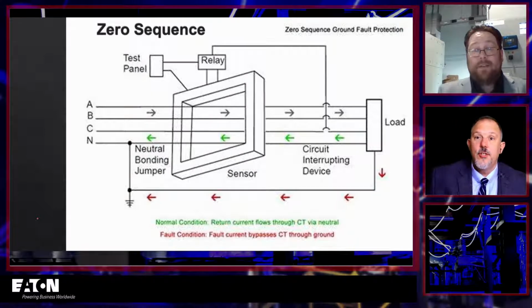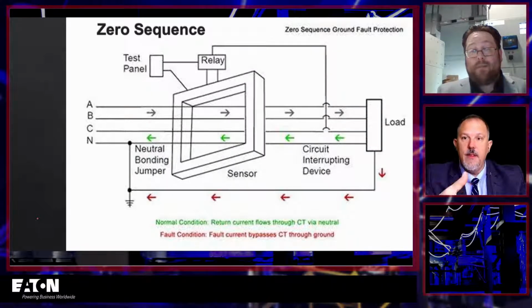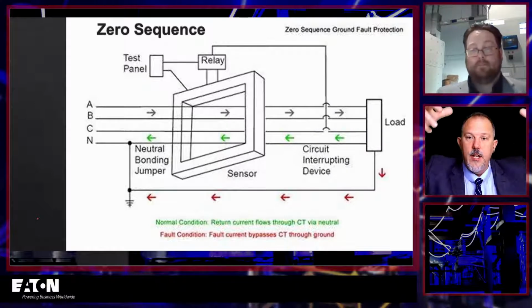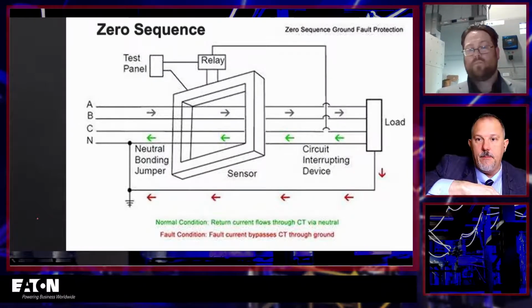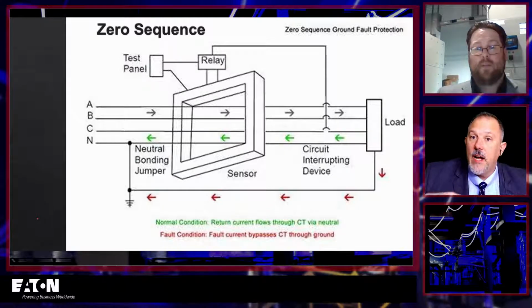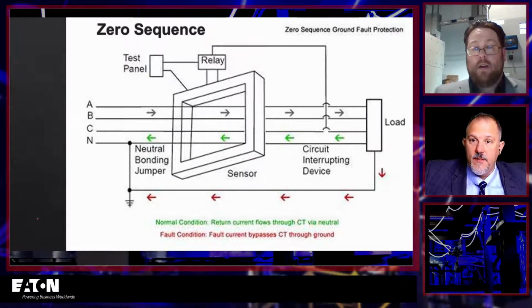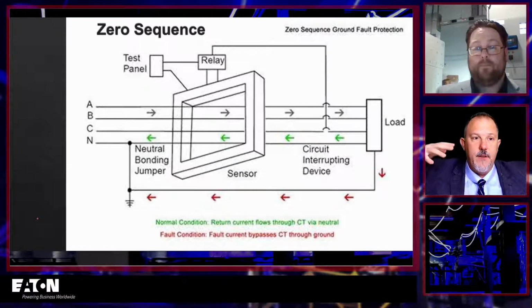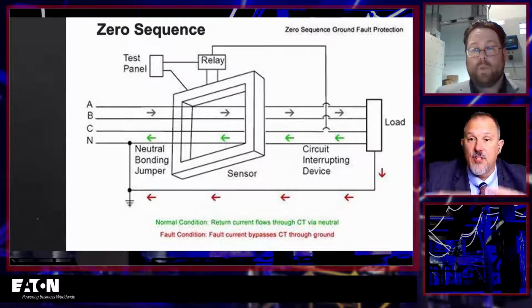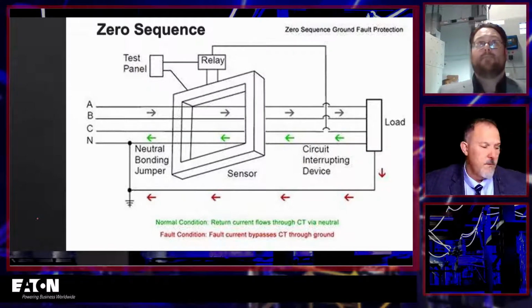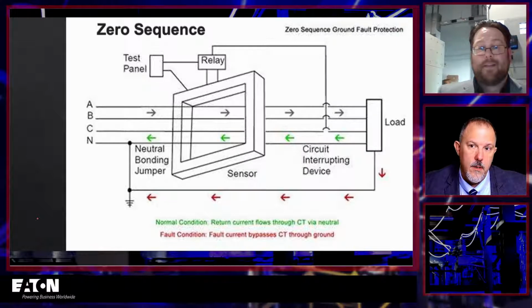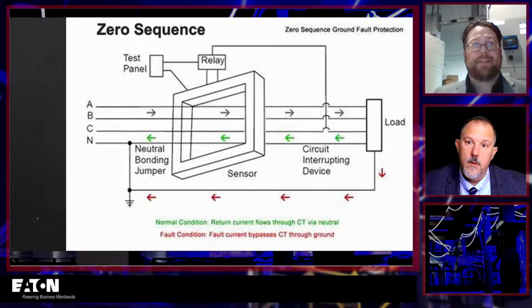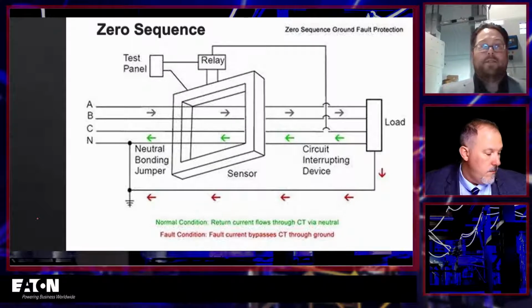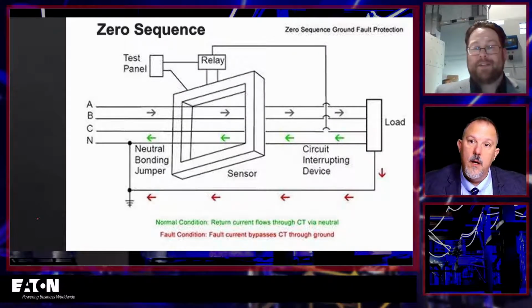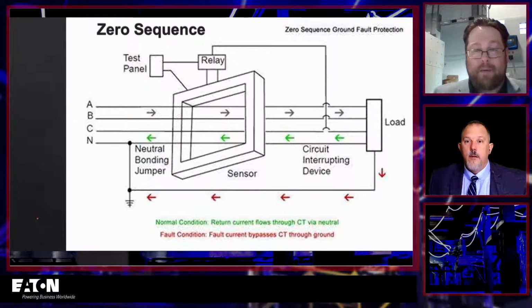Right. So you really are going to be in the equipment. You're going to be clamping things to inject current in certain areas of that bus. Do you have to isolate anything else? I mean, is there anything I have to think about outside of that box? So you need to think about, are there any other paths that you're not necessarily considering? Generally you would open all of your feeder breakers just to ensure that that phase current doesn't actually go somewhere else and come back through another path.